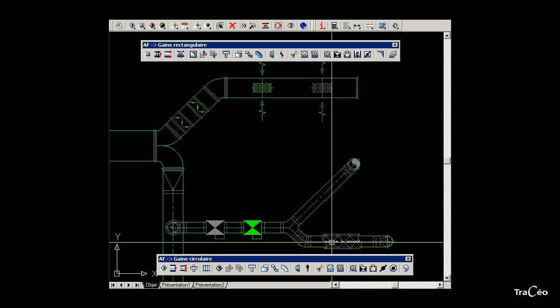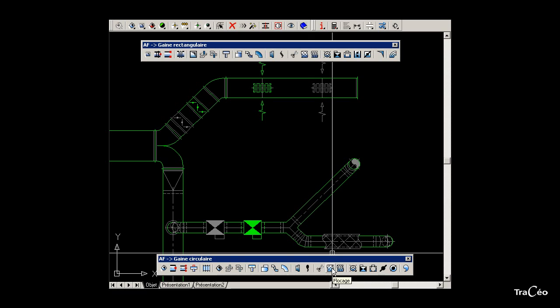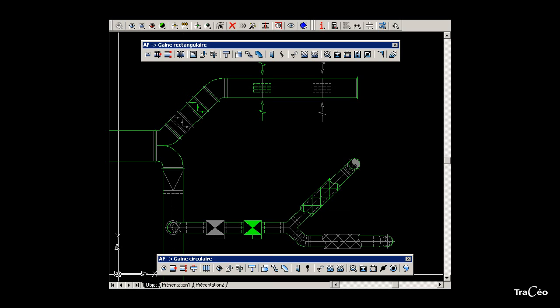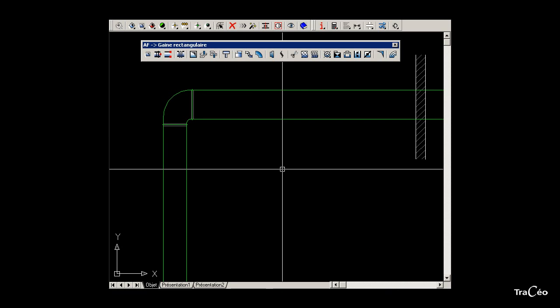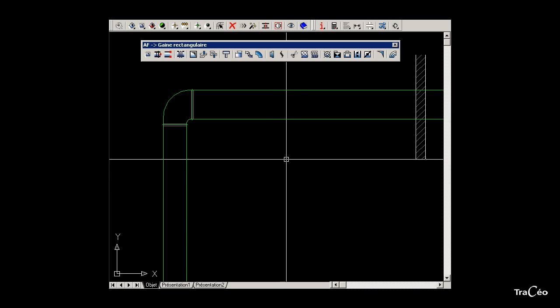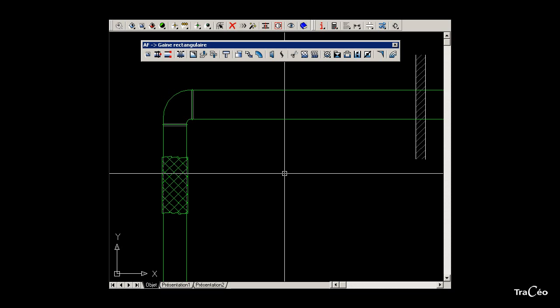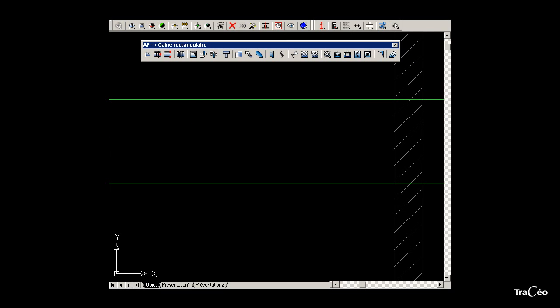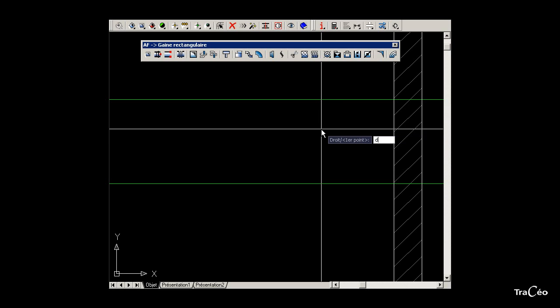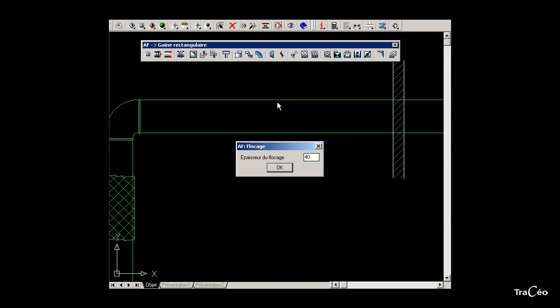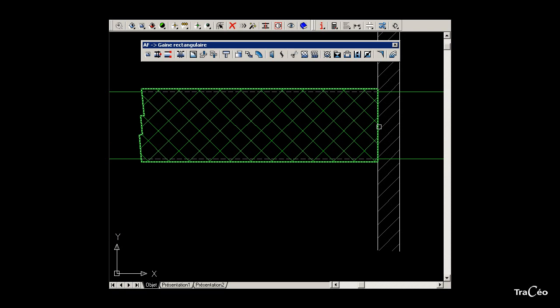To add flocking or insulation, use the insulation command from the circular duct toolbar. Click to indicate a first point, then a second point. Specify the thickness of the insulation and the command is over. Applying flocking can be done in two ways: one piece of flocking that indicates the whole section is insulated, or by precisely indicating where the flocking starts. Use the same command but with the option right. Press D and click to specify two points where the insulation starts. Click the third point and insert the thickness. Now the insulation is accurate on the side you specified.